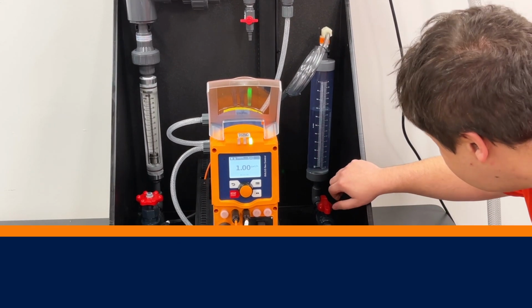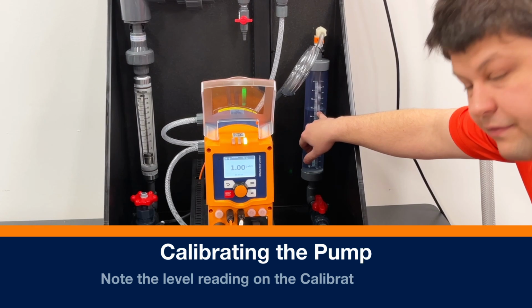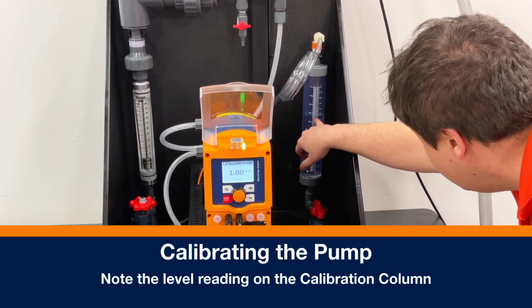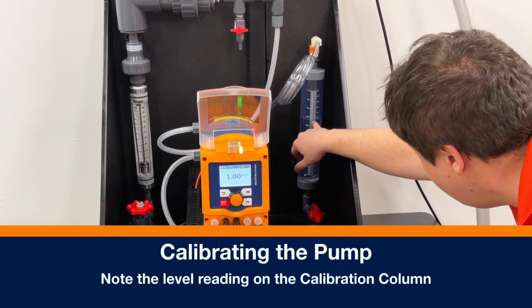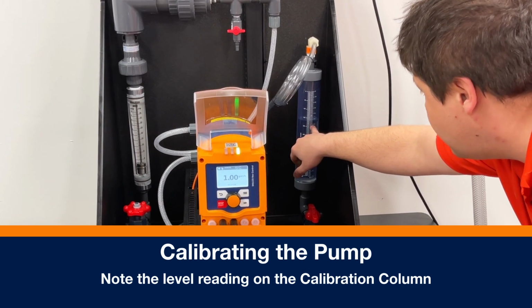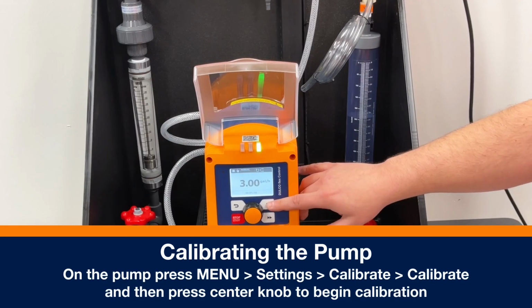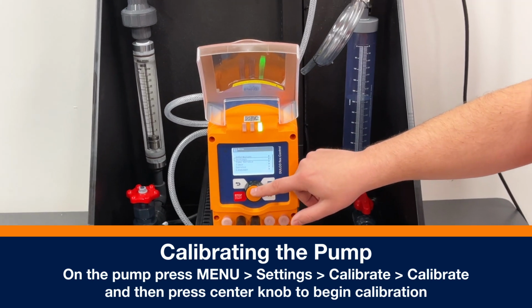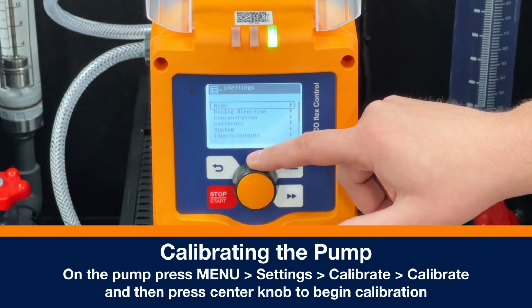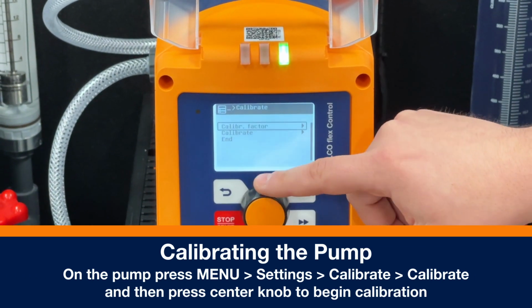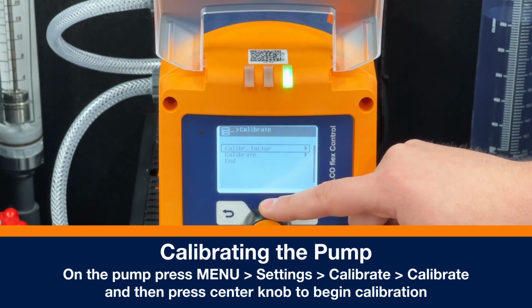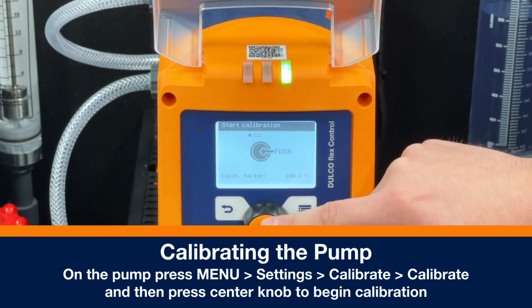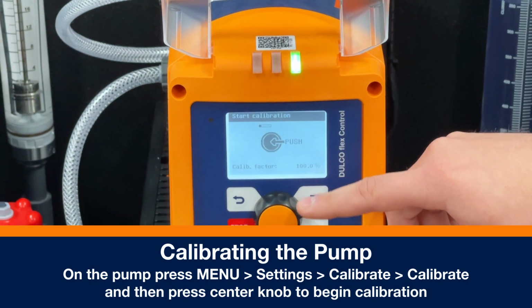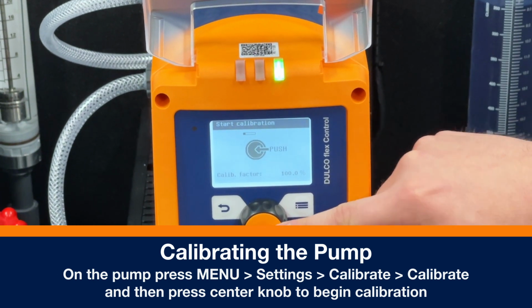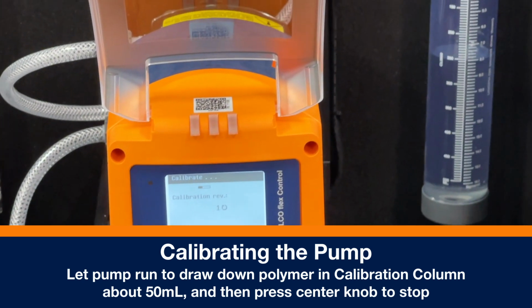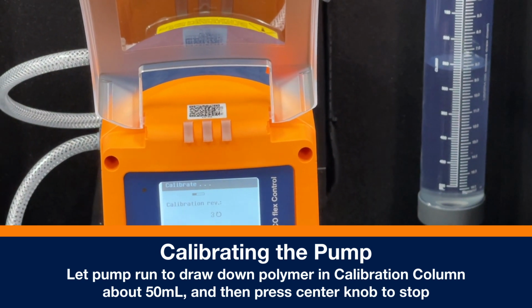Next, we're looking here at the calibration column. So right now, after priming the pump, we're down to about 5.2 on the gallons per hour side. We're going to come in on the pump. We're going to press the menu key. We're going to go to settings. We're going to come down to calibrate. We're not worried about the calibration factor. We're just going to go straight to calibrate. And then it's going to ask you if you want to press the calibrate. We press the center knob here. And we're going to let it run for about 50 milliliters through this.